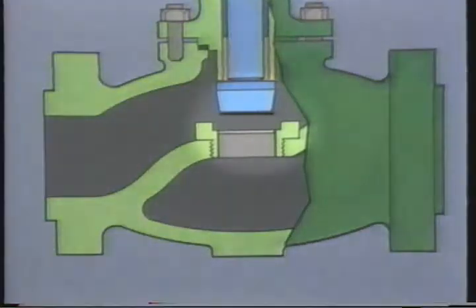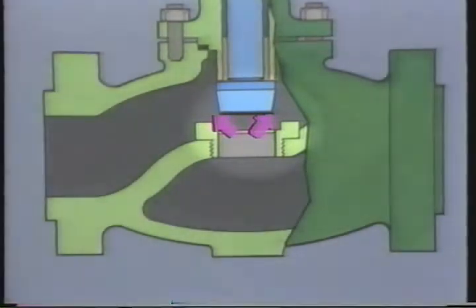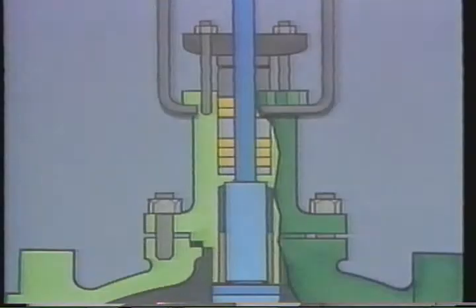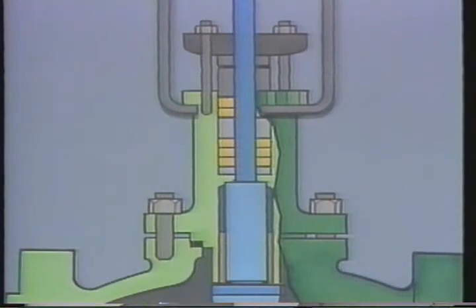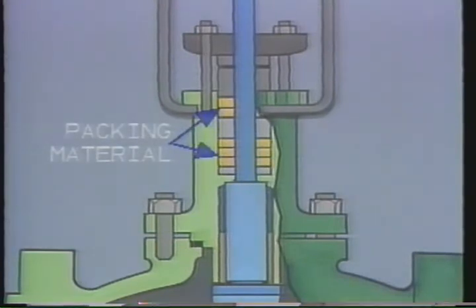In a globe valve, the area of the valve opening between the seat and plug determines how much processed fluid can flow through. Now let's look at the parts that guide the movement of the stem when the valve is in operation. The packing assembly is contained in a stuffing box. One part of the packing assembly is the packing material. Packing material helps guide the stem and keeps fluid from leaking out along the stem. Sometimes packing materials are lubricated to reduce friction.